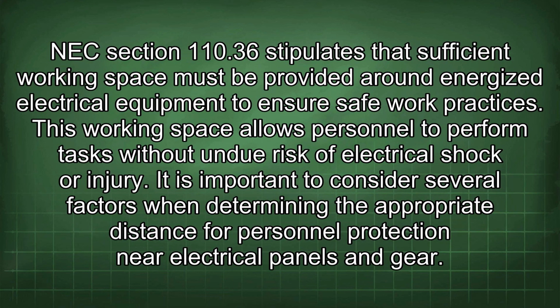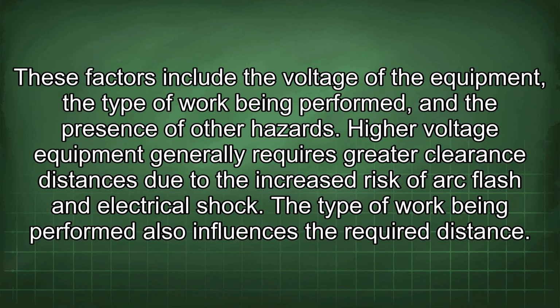NEC Section 110.36 stipulates that sufficient working space must be provided around energized electrical equipment to ensure safe work practices. This working space allows personnel to perform tasks without undue risk of electrical shock or injury. It is important to consider several factors when determining the appropriate distance for personnel protection near electrical panels and gear. These factors include the voltage of the equipment, the type of work being performed, and the presence of other hazards. Higher voltage equipment generally requires greater clearance distances due to the increased risk of arc flash and electrical shock.